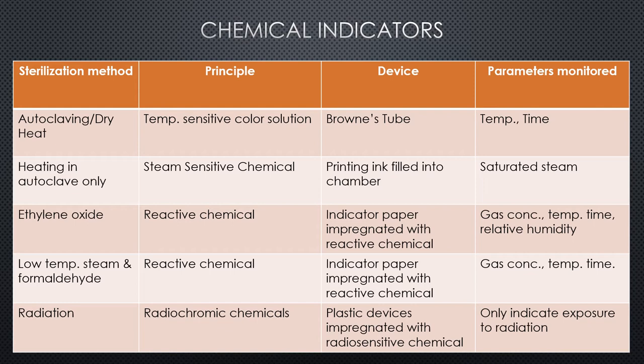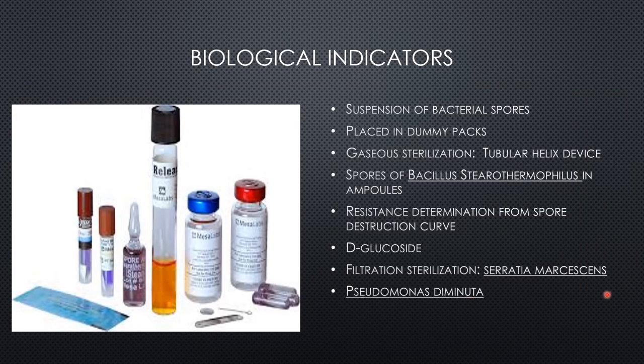For radiation sterilization, radiochromic chemicals are used as the basic material. Plastic devices impregnated with radio-sensitive chemicals undergo a color change at relatively low radiation doses. The parameter indicated is only exposure to radiation. These are the different types of chemicals used for different sterilization methods — either complete melting of the indicator material or a drastic color change occurs, indicating whether sterilization is complete or not.